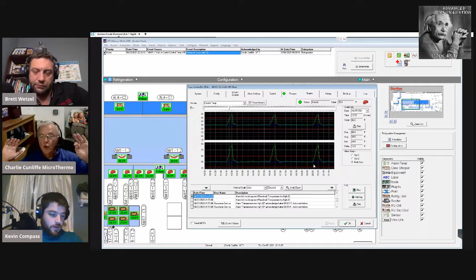Sorry, right, Kevin, because you're right, Brett, this is compound. So imagine 150 nodes in the store, right? If they're all over the place, then your load coming back to the rack is going to be bouncing all over the place. So now your rack is going to be unstable. So that's the key. Start at the evaporator. Get that stabilized. Don't give it an ounce more refrigerant than it needs to do its job.